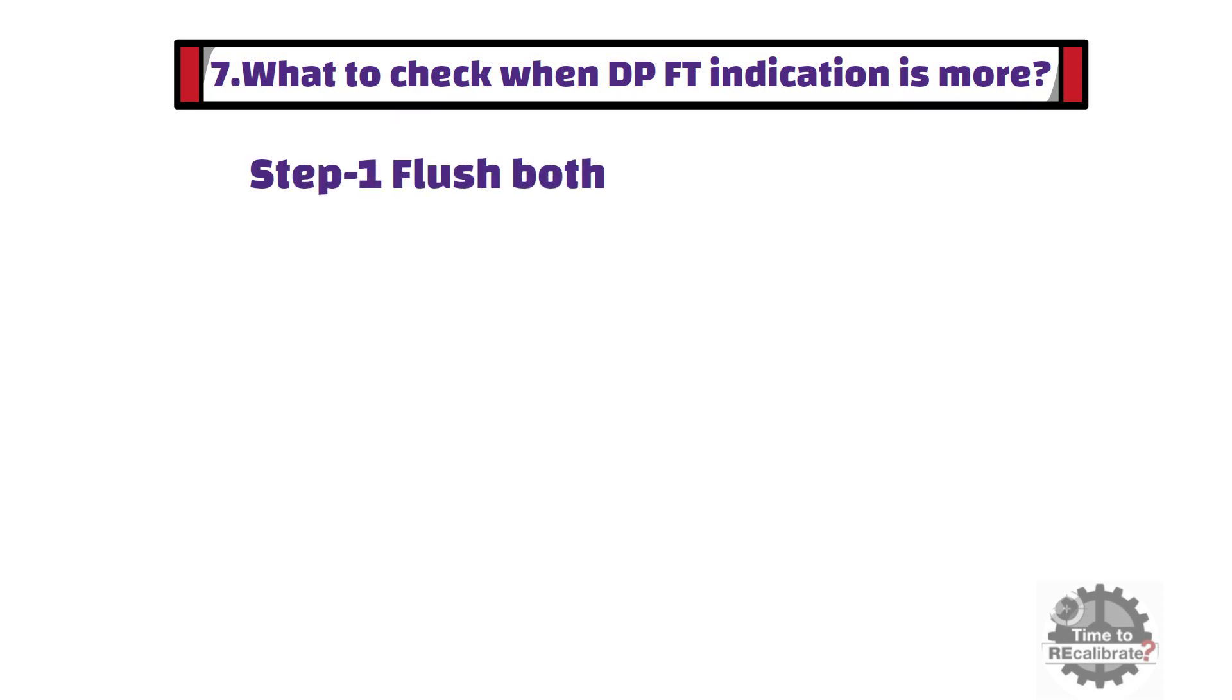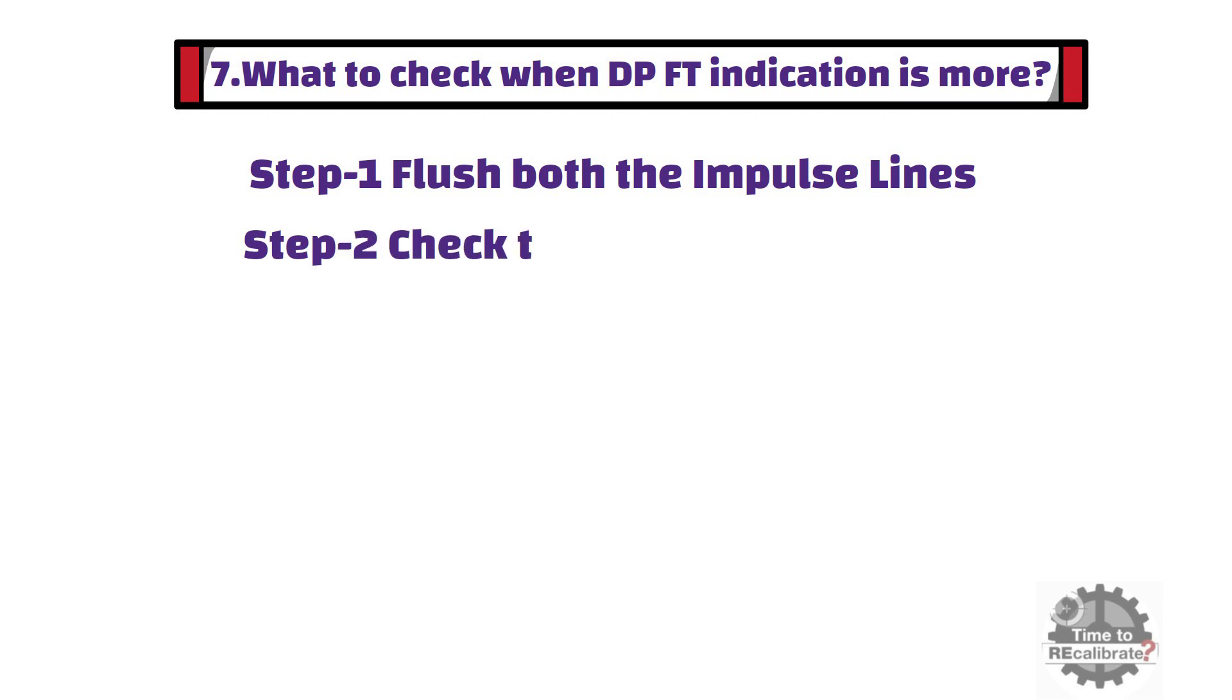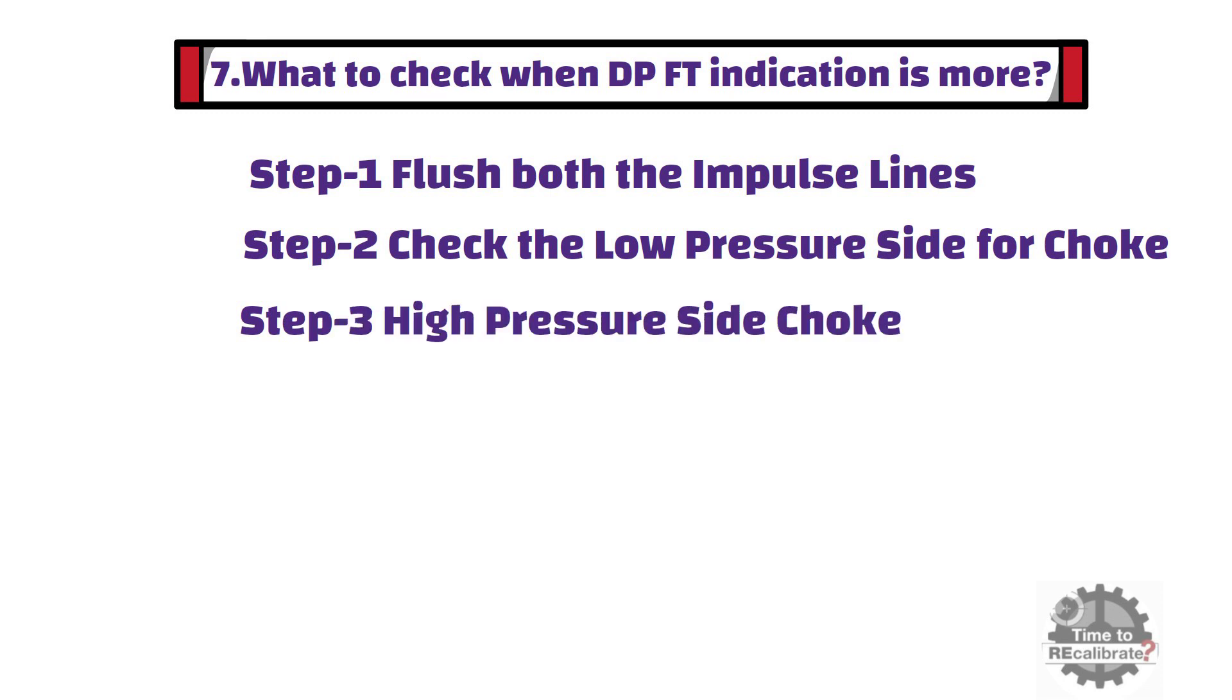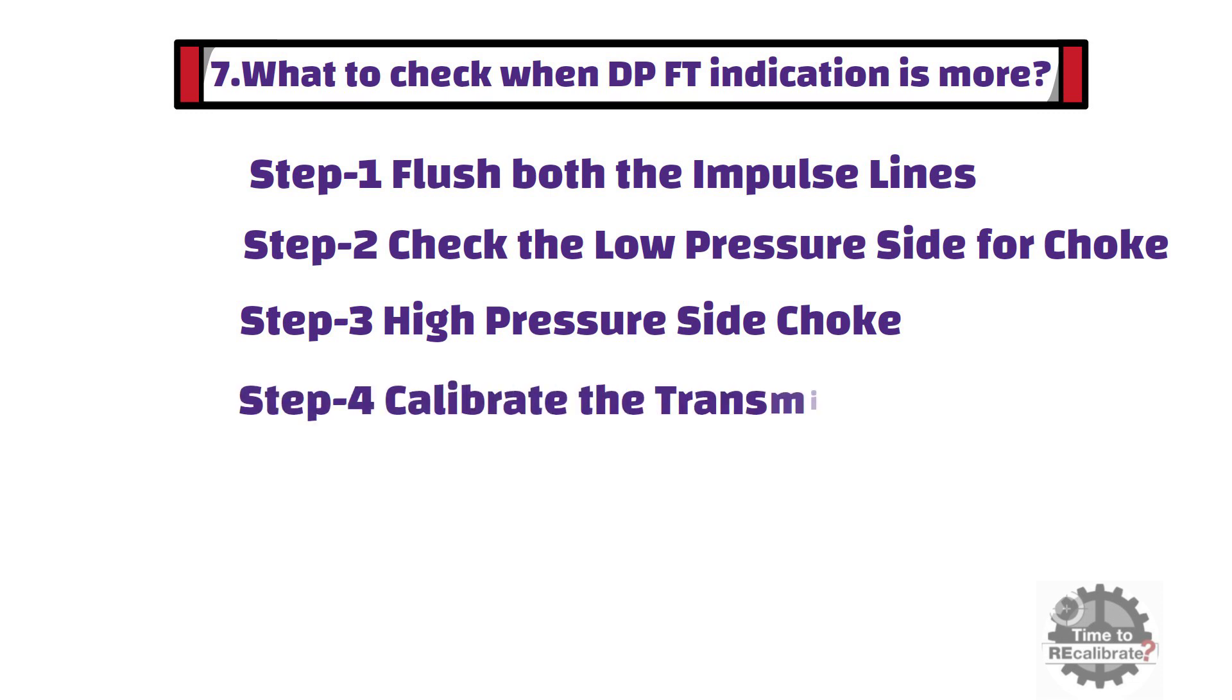In the first step, I will flush both impulse lines and adjust it to zero by equalizing if necessary. If still indication is more, then I will check the low pressure side for choke. Then I will check the high pressure side for choke. Lastly, I will calibrate the transmitter.